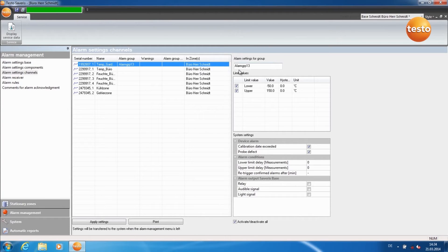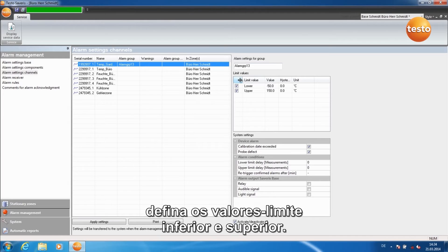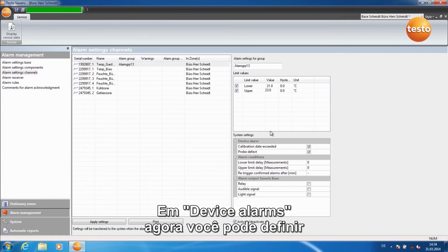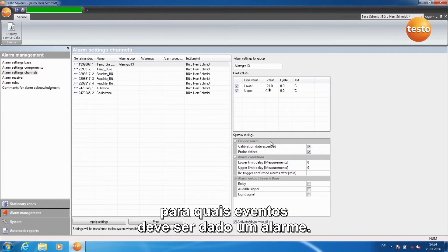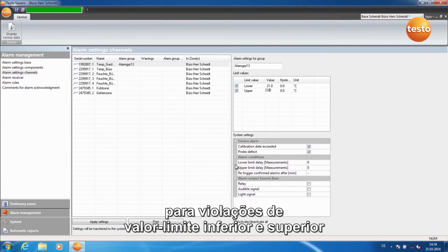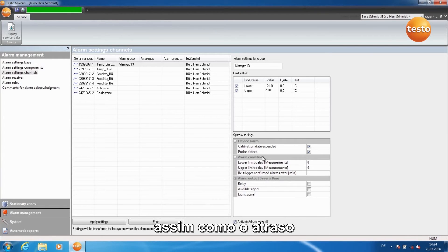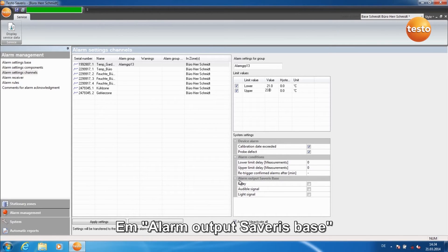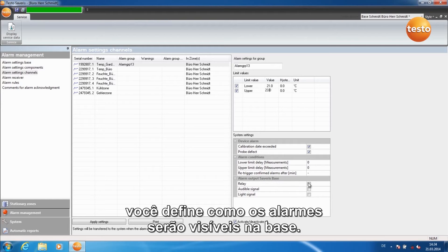Name your alarm group. For limit values, define upper and lower limit values. Under Device Alarms, you can define for which events an alarm should be given. Under Alarm Conditions, you set the delay for upper and lower limit value violations, as well as the delay after which confirmed alarms should be re-triggered. Under Alarm Output Saveris Base, you define how alarms are made visible at the base.